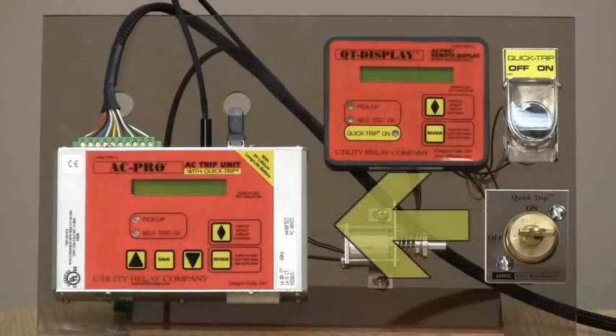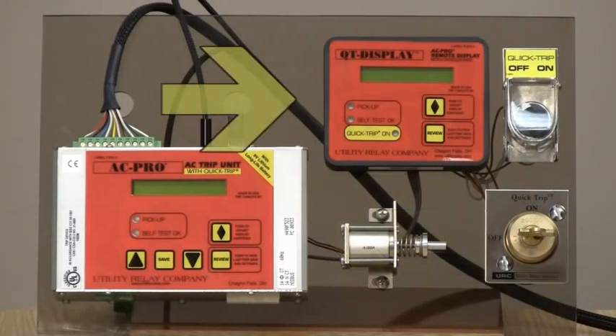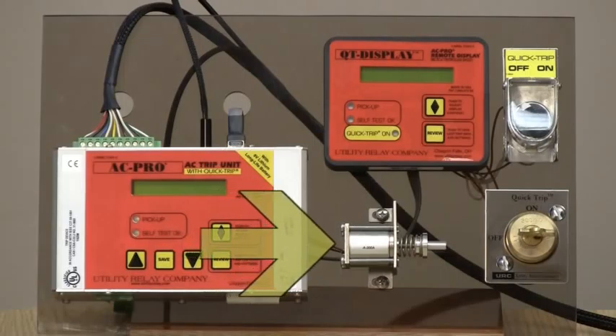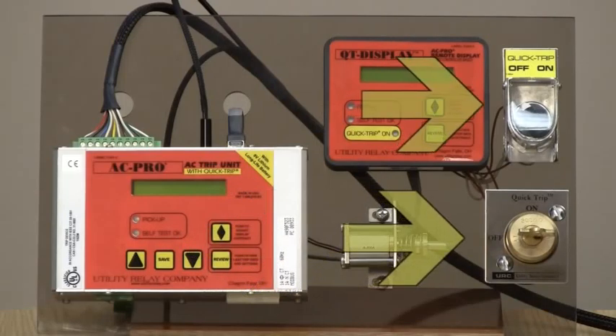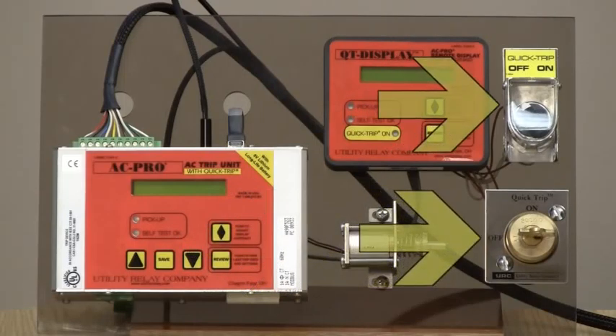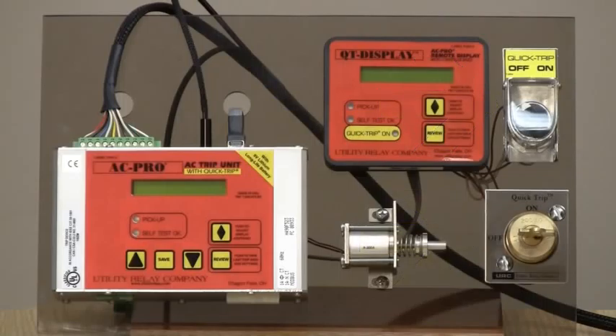This demo has the AC Pro trip unit, quick trip display, an actuator, and 2 versions of the quick trip switch, all mounted together so you can see how all of the parts interact. Usually only one of the quick trip switches and the quick trip display would be mounted on the outside of the cubicle door. The AC Pro and the actuator will be mounted on the breaker itself.